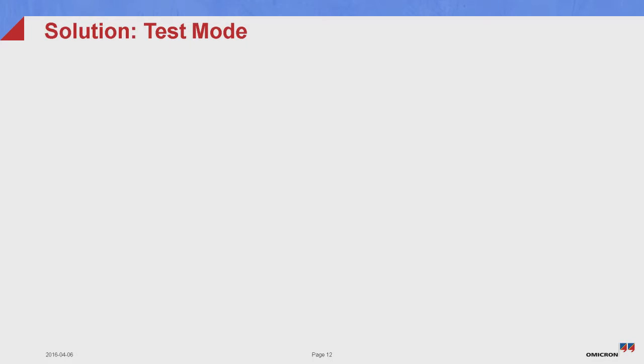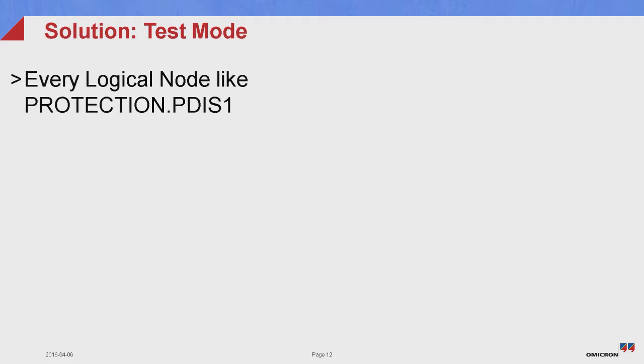And when you discuss with people, they say, yeah, I know there is a test bit in IEC 61850. And this sounds really great, because it's something we already had in the 103, a little test indication, and then the SCADA system, for instance, is not showing the information anymore. It sounds really good. But just remember, we are doing IEC 61850, so the things are a little bit more complex than before. And here, it's really complex.